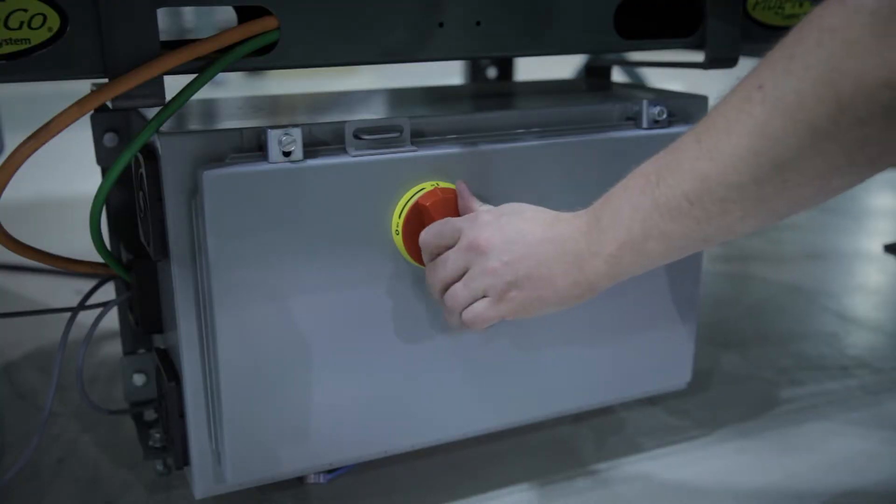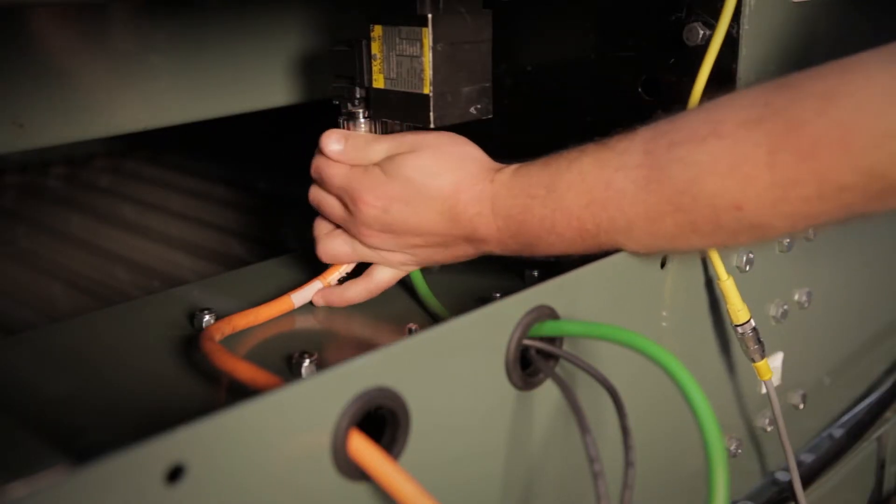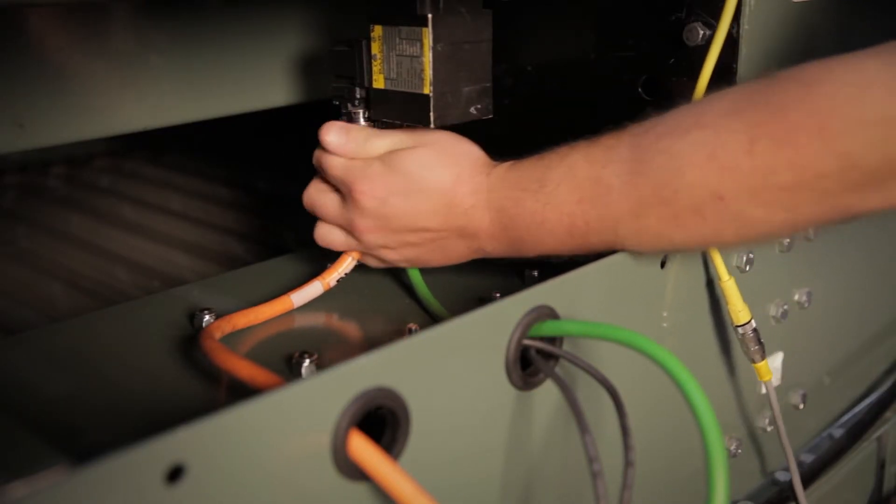Following all lockout-tagout procedures, turn the disconnect on the front of the panel to the off position to disconnect the three-phase supply power and control signal power. Wait at least 90 seconds after removing power to allow it to dissipate to a safe level.